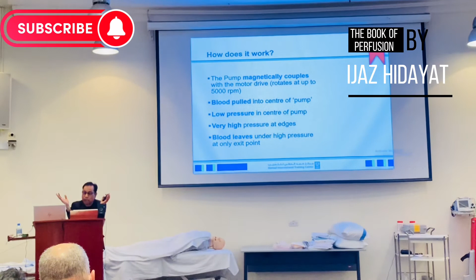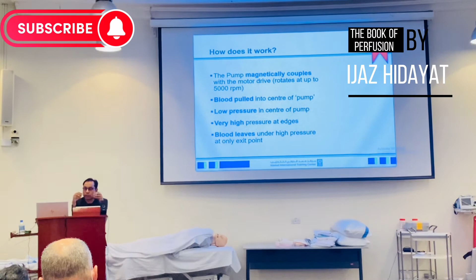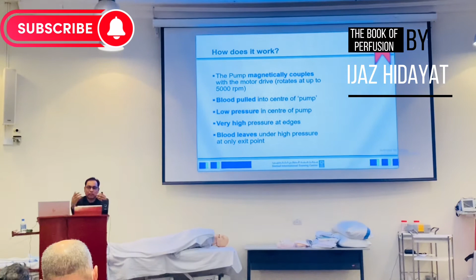But in case there is an occlusion, it is not going to blast. But if you are using the roller pump and there is an occlusion, it is going to blast. There is a chance of rupture of the tubing. But the centrifugal pump is the very safest pump. So in case of blockage, it will not rupture.